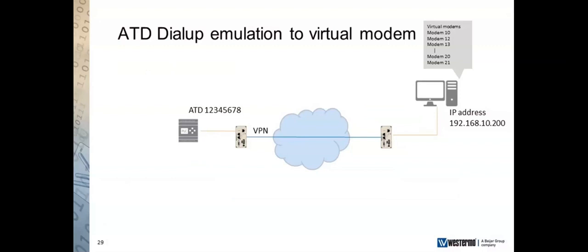It's called a totem pole within the applications layer, where these modems are all ganged up one on top of another, if you like, in memory. But this time when you dial, again you get the ATD, and that's converted to an IP address. But now that opens a socket directly to the virtual modems in the SCADA system.